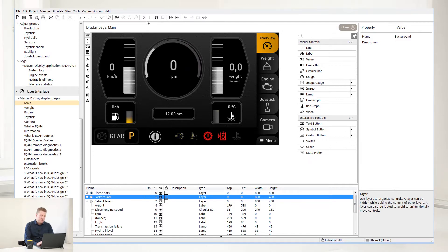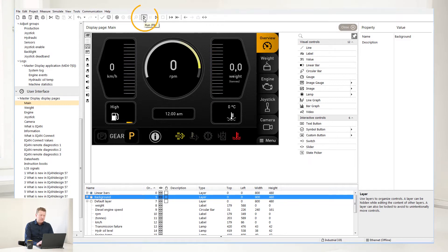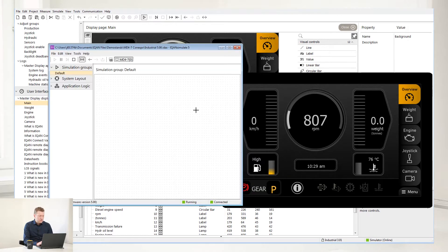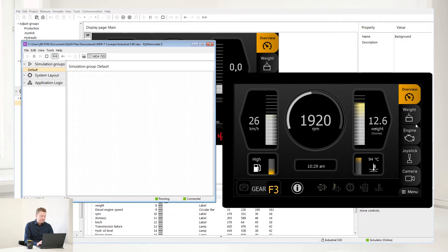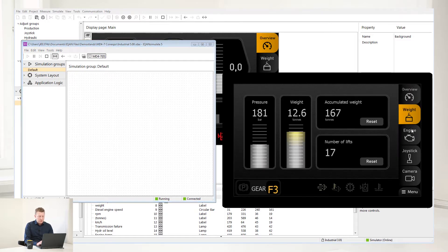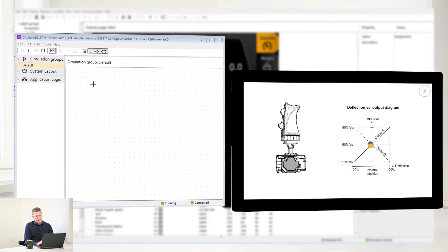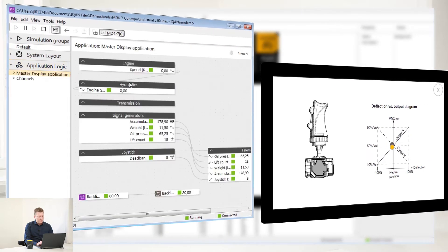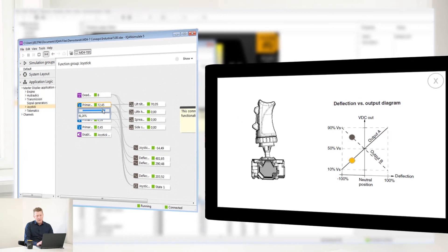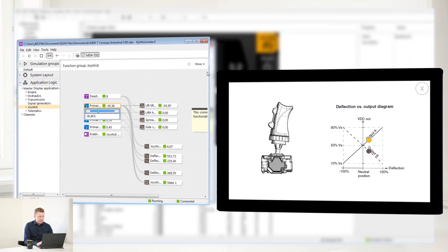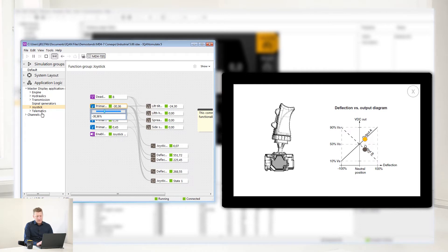At any time during your development you can start to simulate your application. To do that, just click the run icon which starts up the simulation in the background. Select new simulation to activate an exact simulation of the application that would be run in your simulation environment. By simulating, you can move around and test your display pages, and also test your application logic to make sure it behaves like it should. If you select the application logic in the display box, you can find the signal controlling the image and use the toggle to see how the image will be displayed. This checks both the graphics and the functionality of the machine.